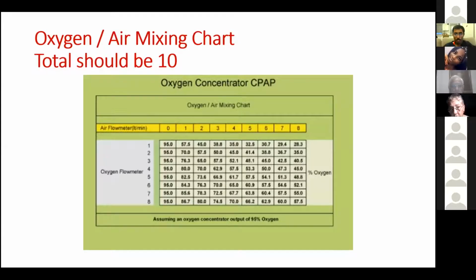Now, this table, which all of you probably know very well, shows how we can change the concentration of oxygen by using the amount of oxygen flow and air flow necessary to increase or decrease the amount of oxygen given to a baby. Altogether, you should give 10 liters. This is like what we do in order to give the CPAP to the baby. Where the saturation is high, we want to change the percent of oxygen by decreasing it. So if we put 5 air and 5 oxygen, the percent of oxygen will be 57.